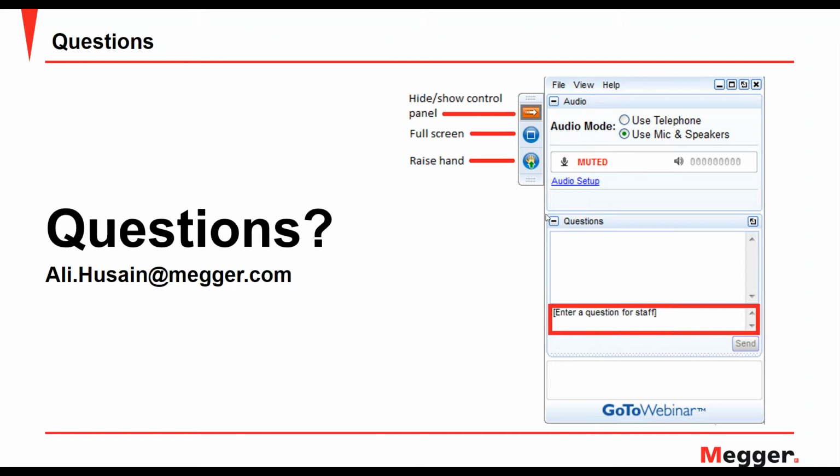Another question also regarding, I believe, the SVERKER900 is how about the step change in the current or voltage channel during increment and decrement of the injection values? For the step change, for the increment and decrement, in this mode it's manually controlled automatically via the knob. If you run it faster, it will accelerate fast, and if you run it smoothly, it will accelerate smoothly.